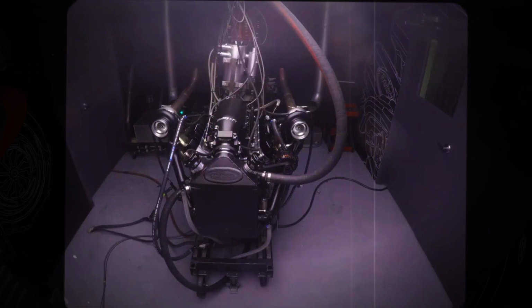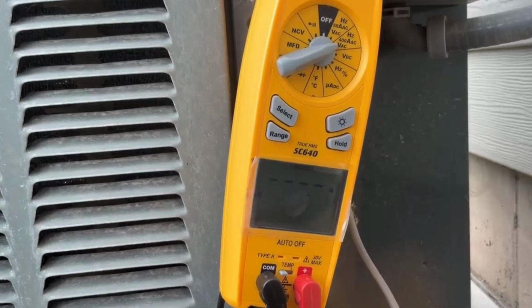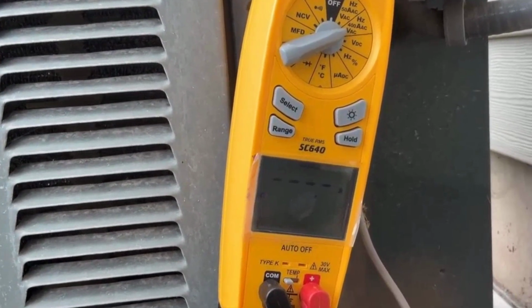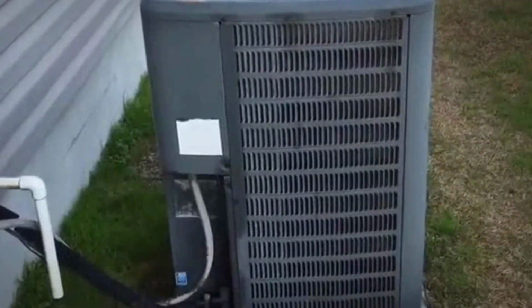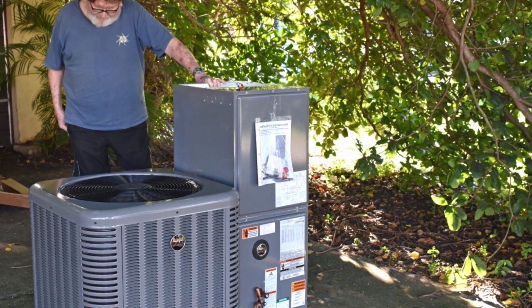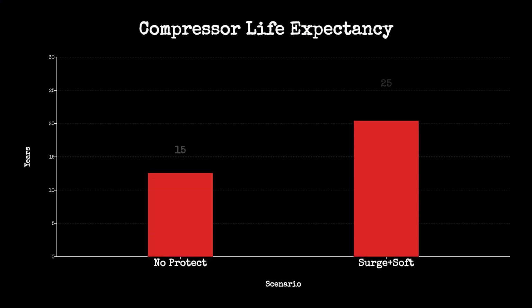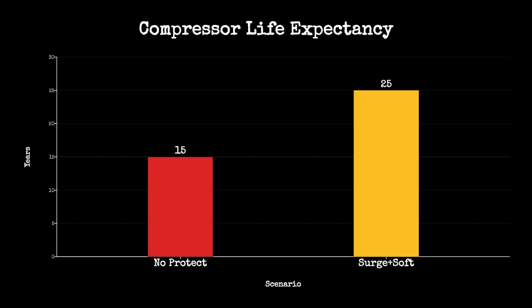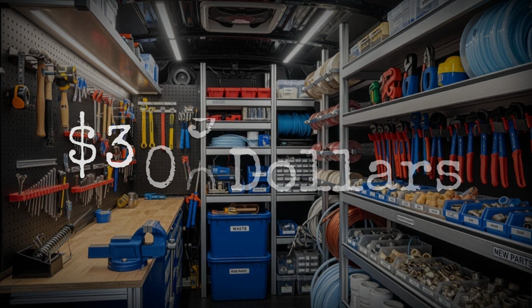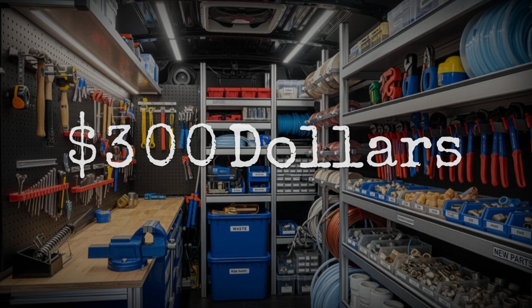Every time your compressor kicks on without one, it pulls 5 to 7 times its running current, like slamming the gas from a dead stop over and over all day. The soft starter ramps it up gradually. Less stress, less shock, longer life. Richard's system ran 15 years without either. That is why his compressor seized at 15 instead of 25. These 2 components, $300 total, can double your compressor's operational life.